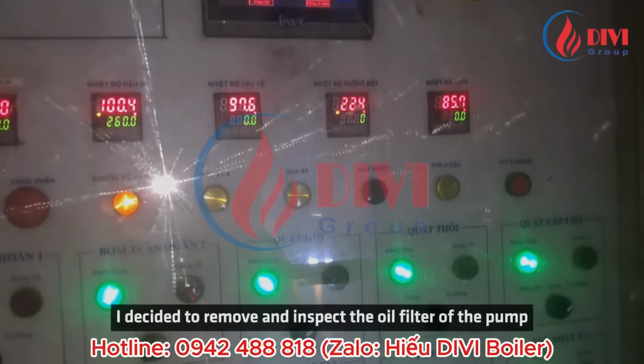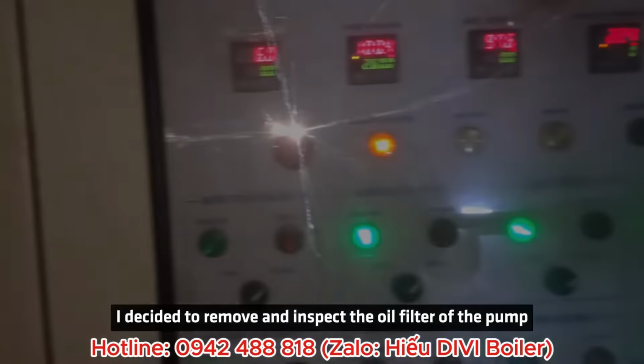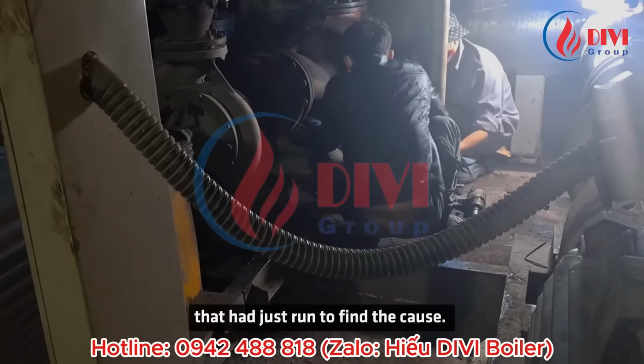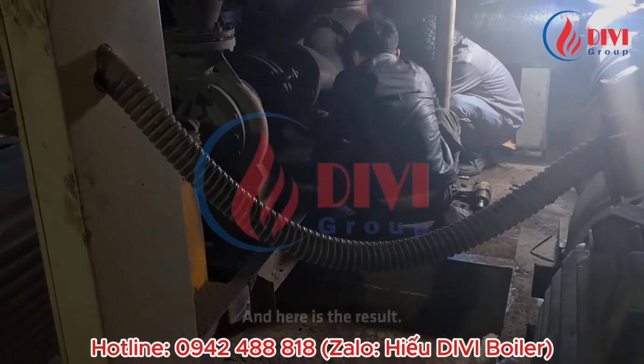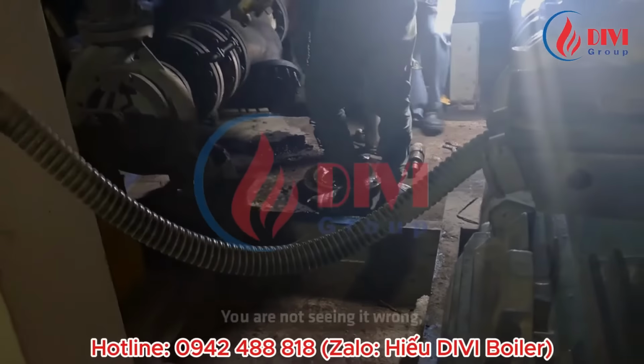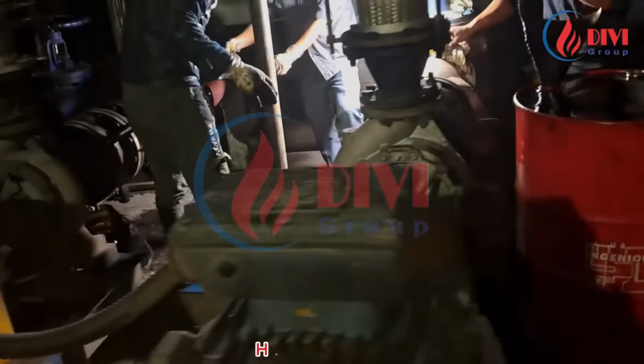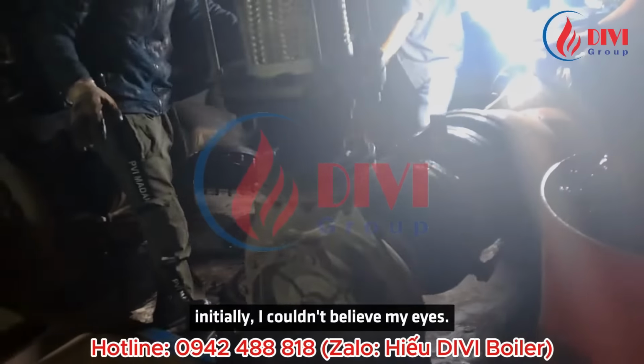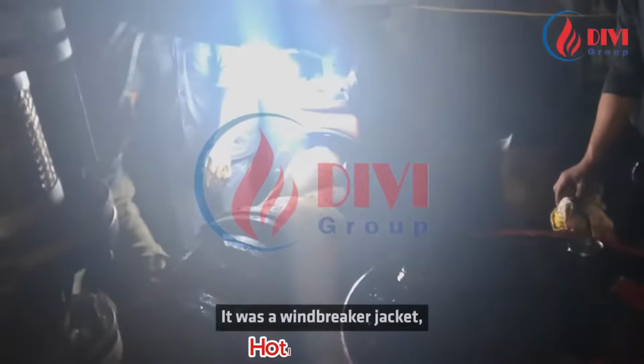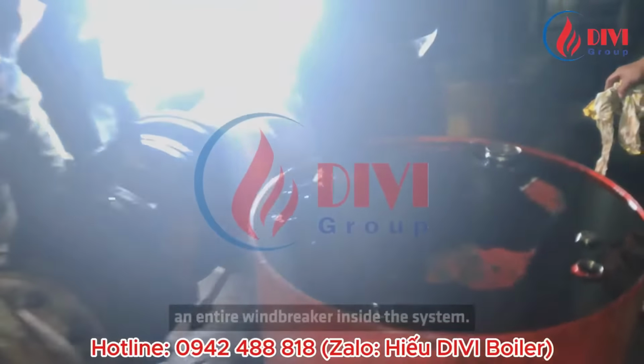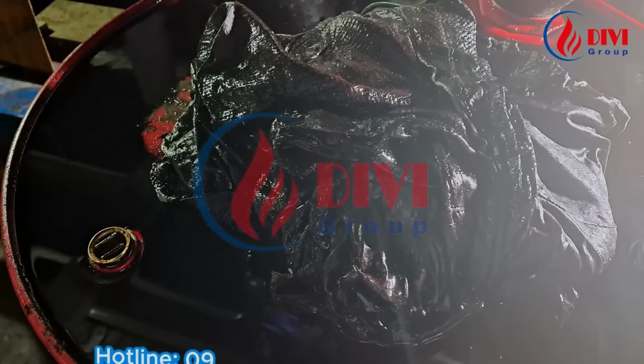I decided to remove and inspect the oil filter of the pump that had just run to find the cause. And here is the result. You are not seeing it wrong. Initially, I couldn't believe my eyes. It was a windbreaker jacket, an entire windbreaker inside the system.